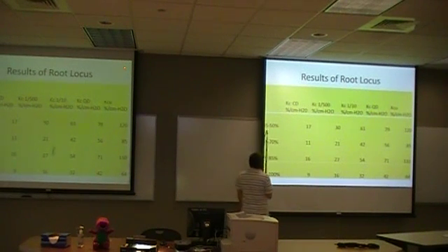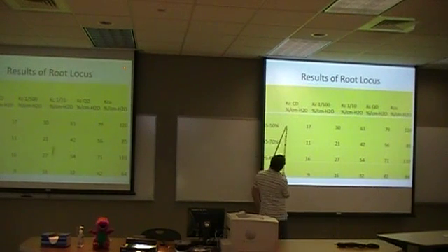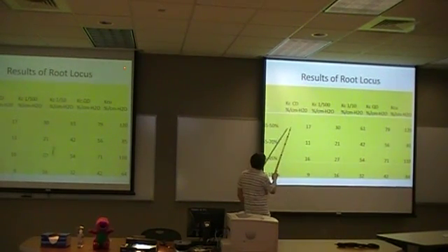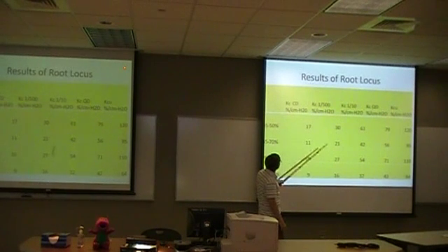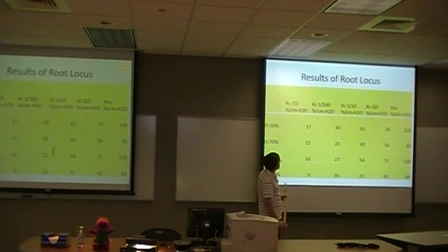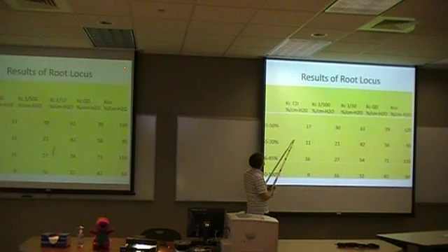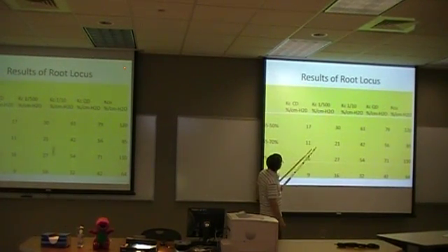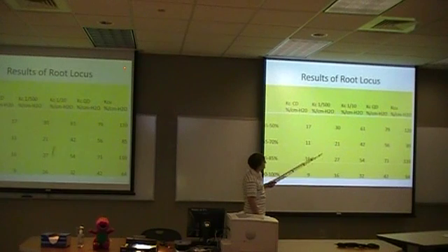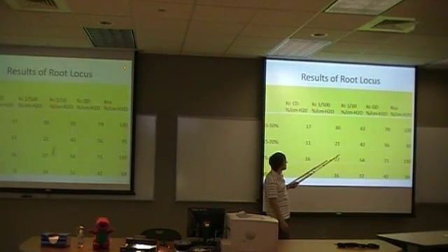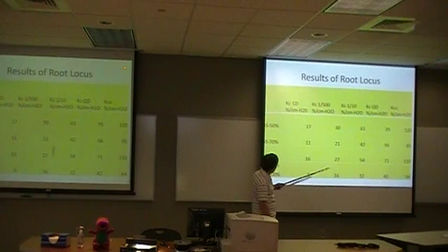So, and that's supposed to be, no, that's right. Okay, so for Brad's range 1 to 4, we got 17 for the critical decay, 30 at the 1/500th decay, 61 at the 1/10th, 79 at the quarter decay, and 120 for your ultimate. For the 4 to 7 centimeter H2O range, we have 11 for the critical decay, 21 for the 1/500th, 42 for the 1/10th, 56 for the quarter decay, and 85 for the ultimate.